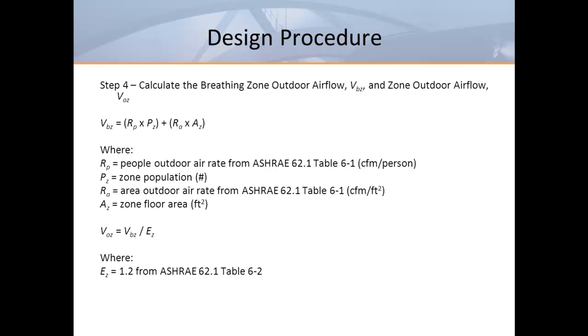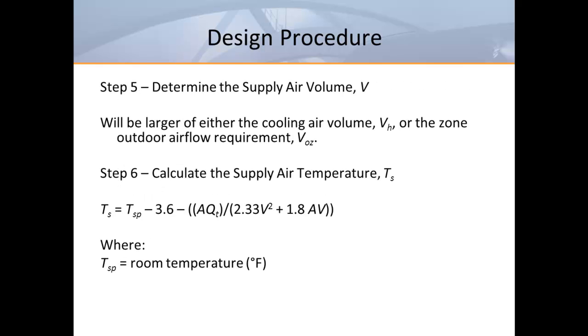I should warn you that even though ASHRAE says that a reduction in fresh air can be made due to the form of ventilation being applied, this reduction may not be recognized by all code enforcement authorities. Now that we know our fresh air requirement, we can determine the supply air volume for our diffusers, which will be equal to our cooling volume. If we're not supplying our diffusers from a dedicated outdoor air system, we can use our fresh air requirement to determine the percent of outdoor air needed at our air handler.